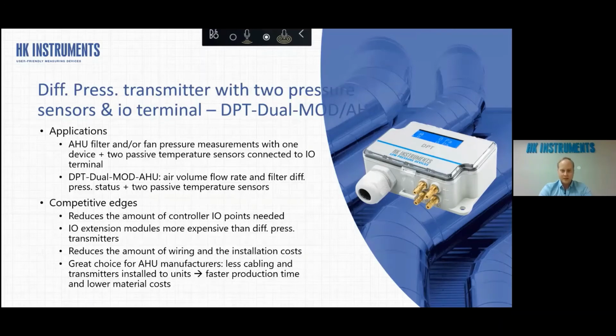Then we have this DPT dual mod AHU, which, as the name says, is focused on the air handling unit and the air handling unit producers, because it has two sensors inside, and the first one is configured for the airflow measurement, so it has these inbuilt formulas inside to convert the differential pressure to the airflow. And the second sensor is just normal differential pressure, and you can connect it to the filter, for example. And in addition, it has these two I/O points. So basically, by putting two of these devices, you can get 4 pressures, or 2 pressures and 2 airflows, and 4 temperatures. So that almost covers every measurement for the pressure and the temperature.